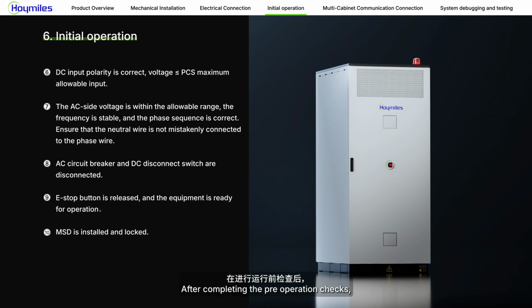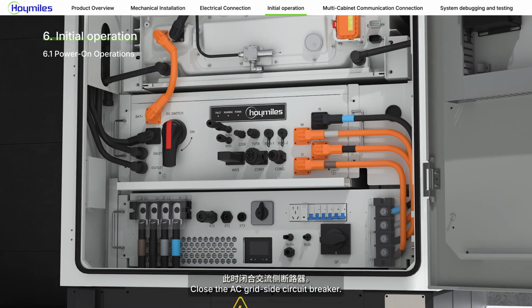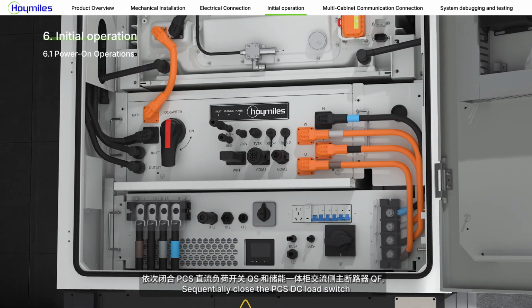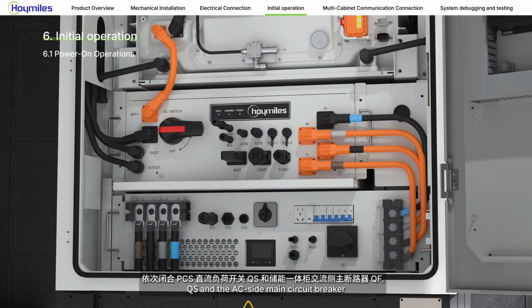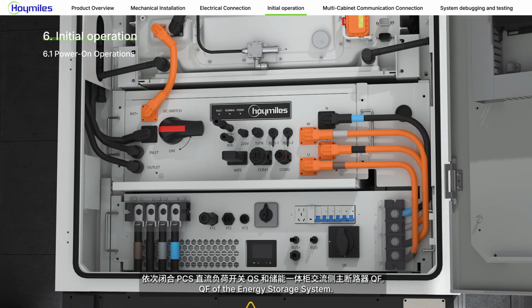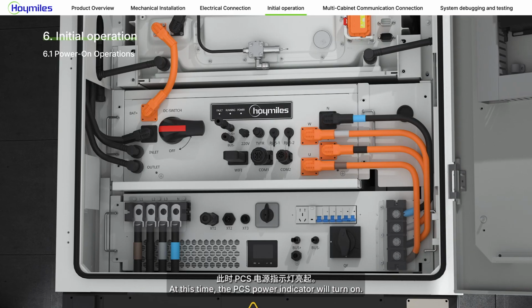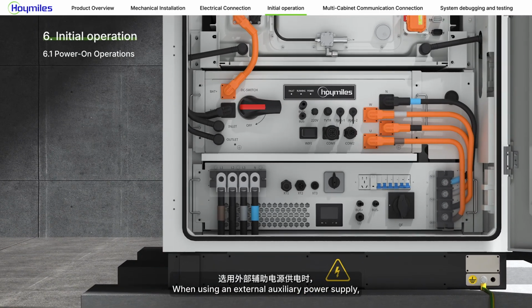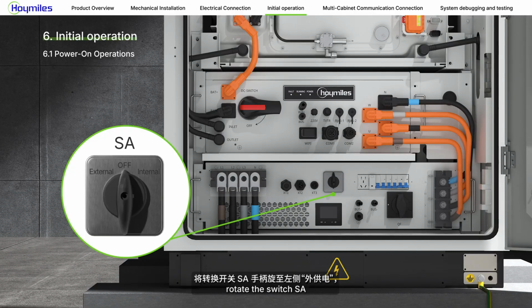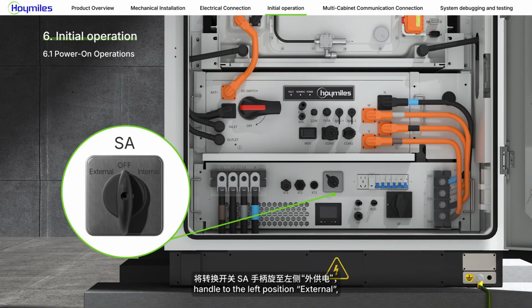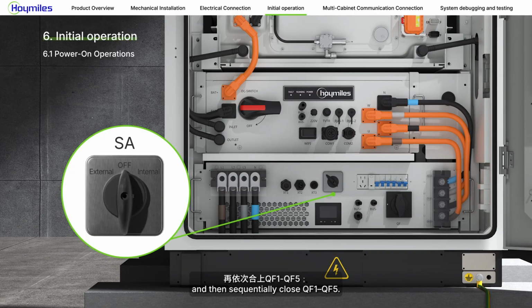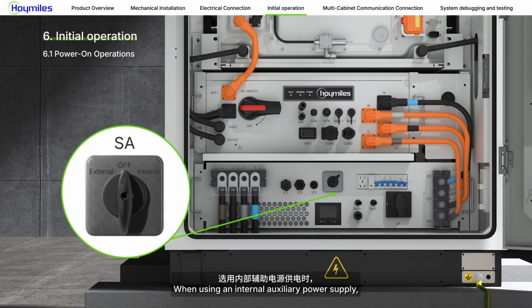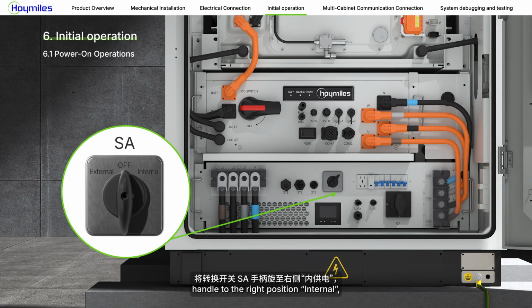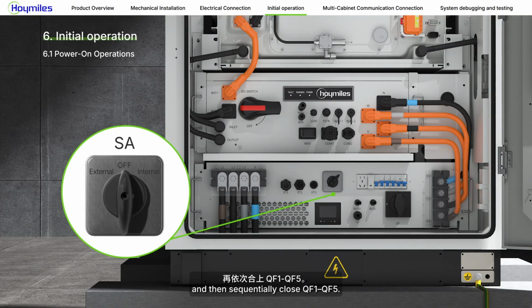After completing the pre-operation checks, ensure that the energy storage system is fault-free and that operator protective measures are in place. Close the AC grid-side circuit breaker. Sequentially close the PCS DC load switch QS and the AC side main circuit breaker QF of the energy storage system. At this time, the PCS power indicator will turn on. When using an external auxiliary power supply, rotate the switch SA handle to the left position, external, and then sequentially close QF1 to QF5. When using an internal auxiliary power supply, rotate the switch SA handle to the right position, internal, and then sequentially close QF1 to QF5.